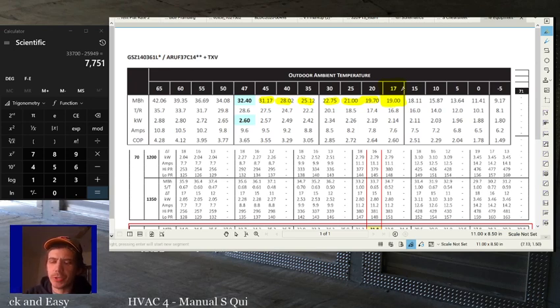I ran into a situation where a 3-ton multi-port mini split could not put out enough BTUs to serve a house, right? Yeah, a 3-ton couldn't do it. But a 2-ton and a 1-ton single unit mini split could handle the load of the entire house. So same manufacturer, same product line, the multi-port outdoor unit wouldn't work, but a 2-ton and a 1-ton indoor would work.